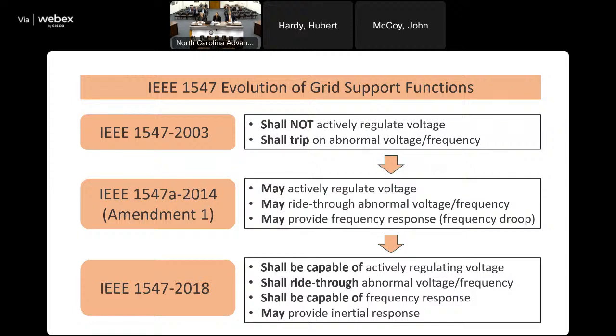A little technical background here: the standard that governs interconnection to the grid is IEEE standard 1547. It came out originally in 2003, so it's been around about 20 years. At that time, solar really wasn't a big deal outside of maybe Hawaii and California. In this part of the country, most of what we dealt with was cogeneration facilities wanting to interconnect and sell power back to the grid. We had some hydro plants being developed along rivers in the state, but there really wasn't a lot of renewables at the time.